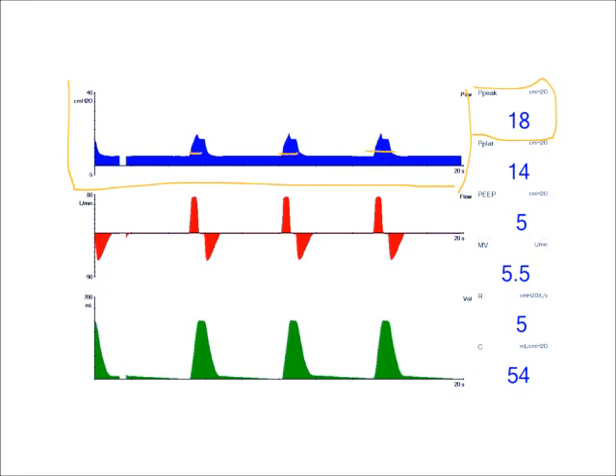During this inspiratory phase, the exhalation valve is closed, and the patient can't exhale unless they reach the high pressure threshold setting. This is usually an alarm setting, and after the alarm setting there is also another safety backup setting.